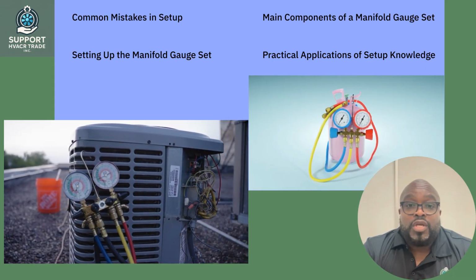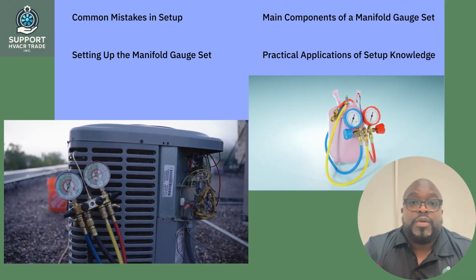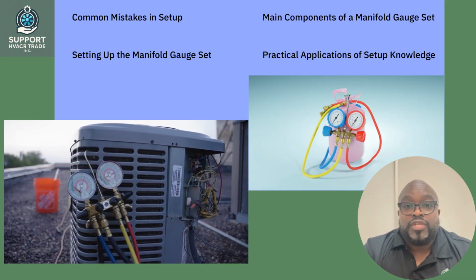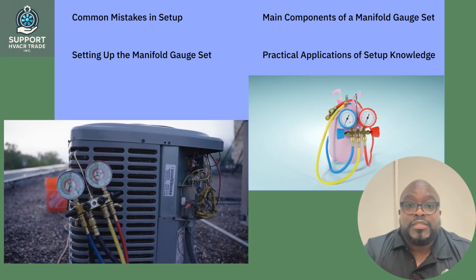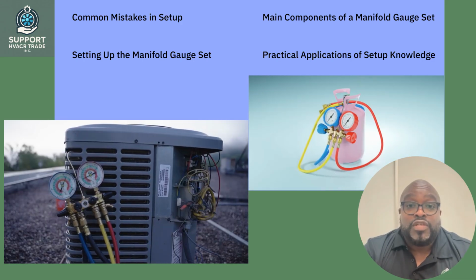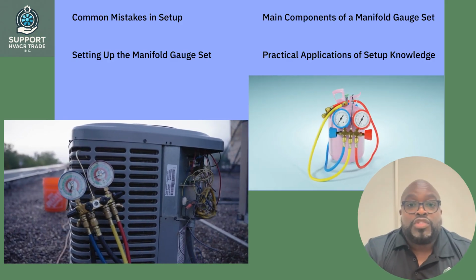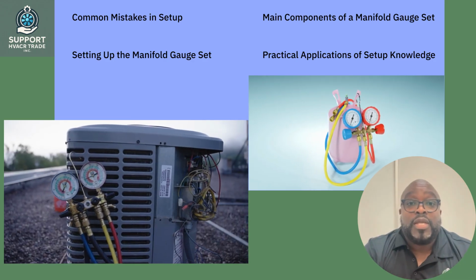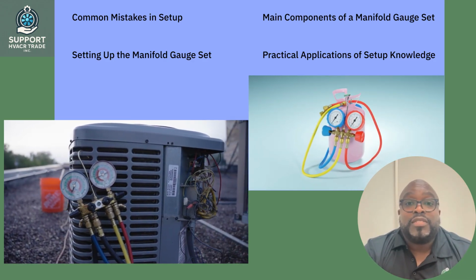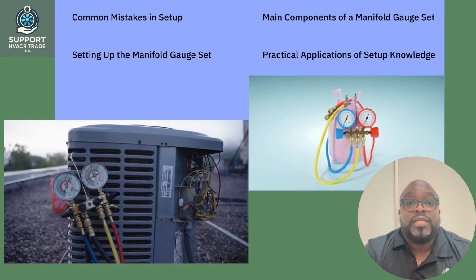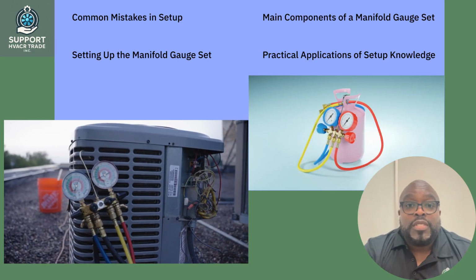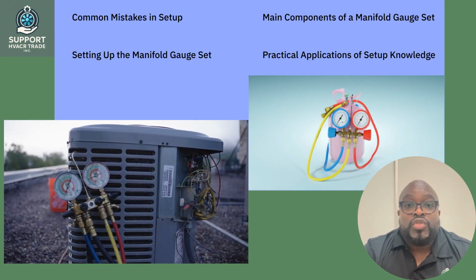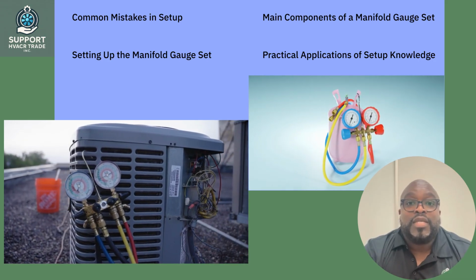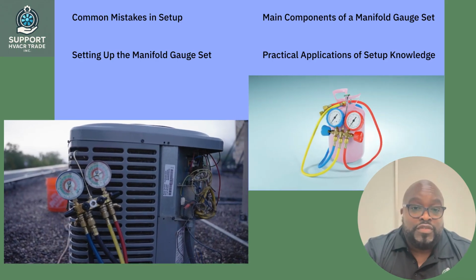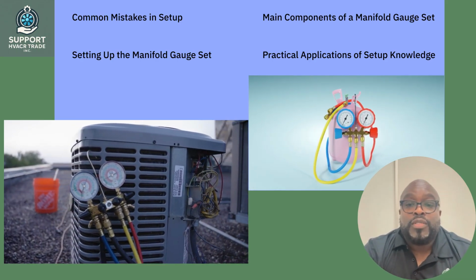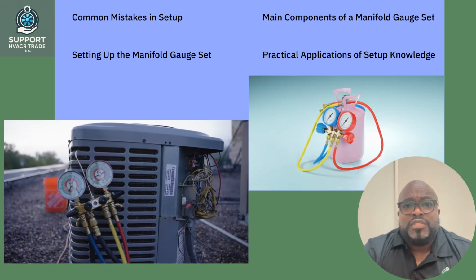Practical applications of setup knowledge. Understanding the components and proper setup of the manifold gauge set directly translates to enhanced diagnostic capabilities in real-world applications. For instance, when responding to a service call for a malfunctioning air conditioning unit, knowing the correct setup allows you to quickly assess refrigerant levels and system pressures, leading to faster resolutions. Consider a scenario where you find low pressure readings. This could indicate a refrigerant leak, allowing you to address the issue promptly. Practice setting up your manifold gauge set in a controlled environment to reinforce your learning. Familiarity with the components and their functions will increase your confidence and efficiency in the field.